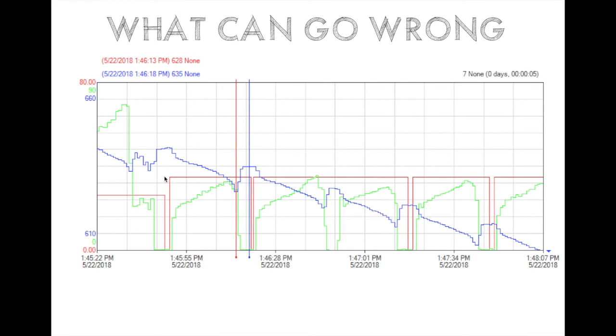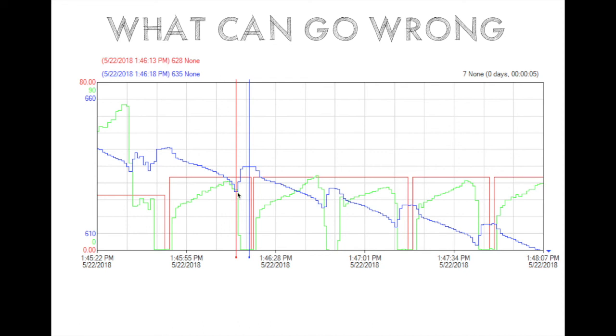And it turns out that another factor that's going on here is that if we zoom in on the hopper weight, which is the blue, so this is zoomed way in and we didn't see it in the previous plots, but it is jumping. There are times where it is gaining weight even though nothing is supposed to be going into the tank. So the difference between this valley and the peak is seven pounds on a value in the 600 pound range.